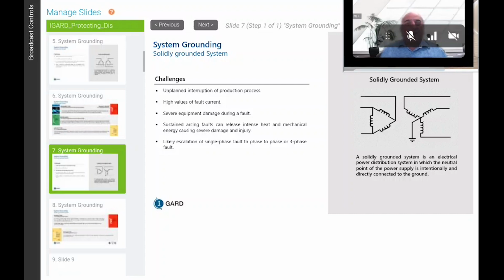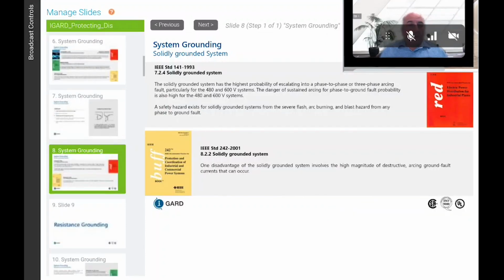When you have a ground fault in a solidly grounded system, and when we go back to the book that came from Dunki-Jacobs, it says that because you have a ground fault in a piece of equipment, usually your ground fault is going to be inside a piece of equipment. You deteriorate the insulation around the point of the fault, where it could quickly develop into a phase-to-phase fault or a three-phase fault, and then you have an arc flash event. According to the red book, solidly grounded systems have the highest probability of escalating into a phase-to-phase or three-phase fault.